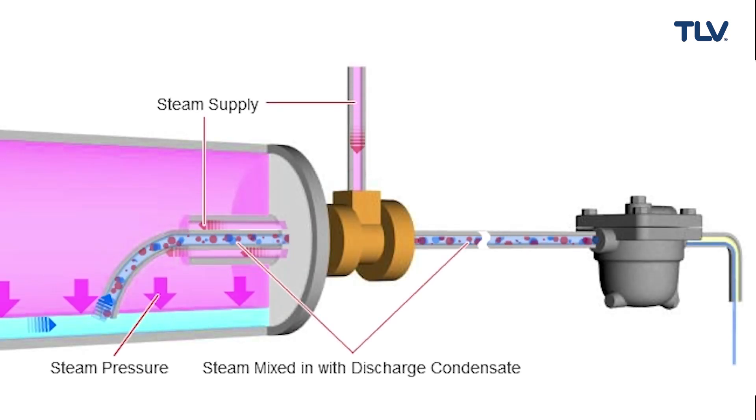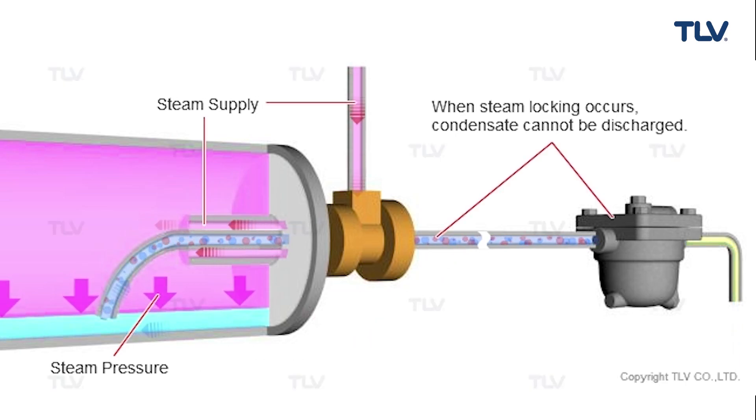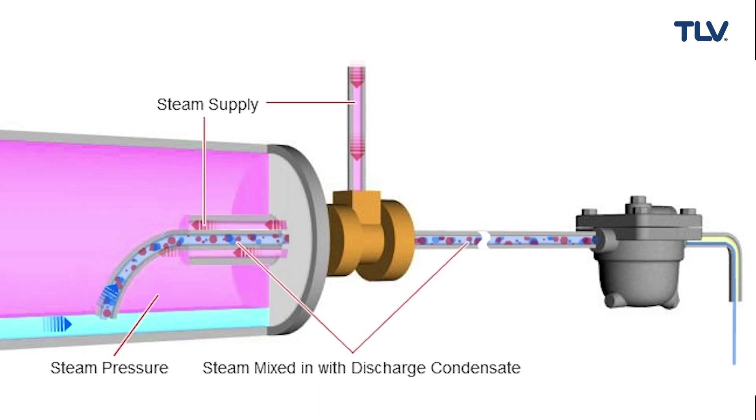When equipment configuration causes steam locking, one solution is to first discharge the steam condensate mixture into a receiver, such as a flash tank, before discharging condensate through a steam trap. The separated steam should then be returned to the heat exchanger for reuse.